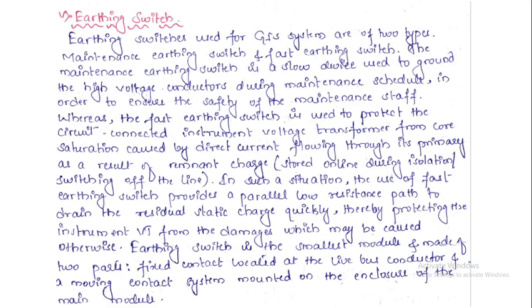The earthing switch is the smallest module and is made of two parts: a fixed contact located at the live bus conductor and a moving contact system mounted on the enclosure of the main module. So this is about the earthing switch.